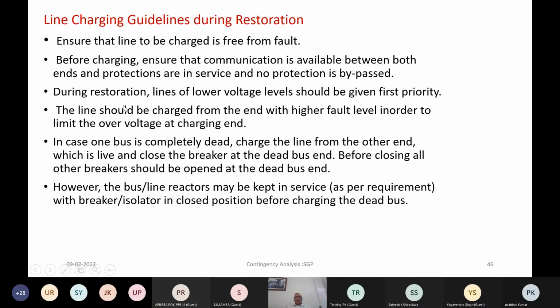These are again some of the steps which are given in the NLDC Black Start procedure. Ensure that a line to be charged is free from fault before charging. Ensure that communication is available to both the ends. During restoration, lines of lower voltage level should be given first priority. That is the bottoms-up approach.